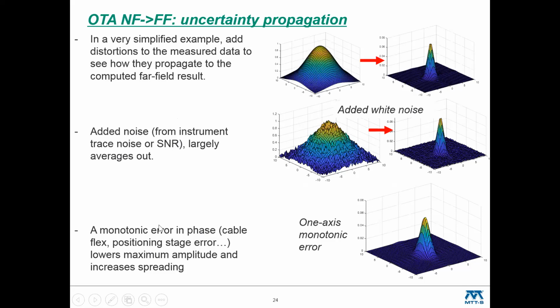But now if we add a monotonic error in phase in one axis, which could be the mechanism we talked about before, you see some pretty significant distortions. We've got some broadening in one dimension. The peak amplitude is much lower than we started. And from just looking at the incoming data, if you only looked at magnitude, you wouldn't think anything was wrong at all. But the transformed result was quite a ways off.